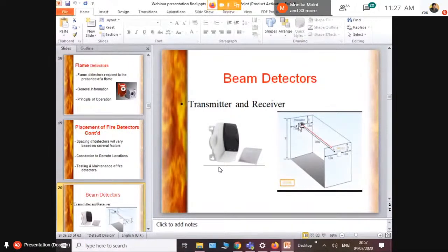From the transmitter, there will always be IR rays being sent to the receiver. The receiver will normally be a mirror, so it takes the signal and gives it back to the transmitter. So it's like give and take. The red line goes all the way to the transmitter and gives back the blue line. That's how it is. I have shown you a small presentation for a height of 11 meters. When you install a smoke detector at 11 meters, the coverage will be less and you have to add multiple smoke detectors there. To avoid that, we can use a beam detector.